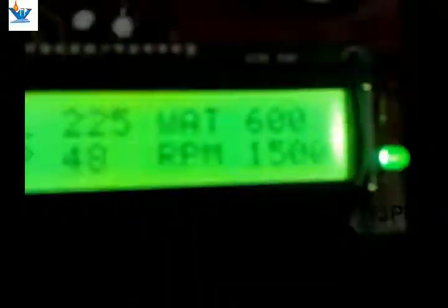Okay, please add one more bulb. The system is set for 1 HP. 750 watt will be okay. Over 750 watt the system will shut down automatically. Now it is showing 600 watt, which is exactly connected at load bank. 3 bulbs of 200 watt.